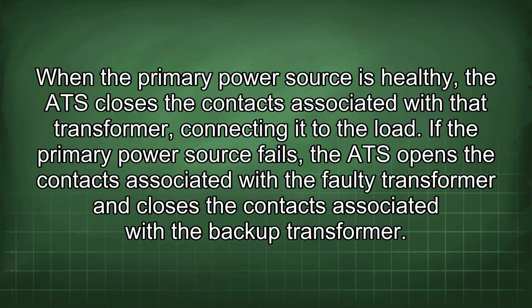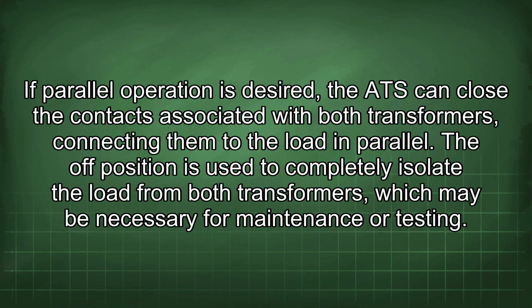When the primary power source is healthy, the ATS closes the contacts associated with that transformer, connecting it to the load. If the primary power source fails, the ATS opens the contacts associated with the faulty transformer and closes the contacts associated with the backup transformer. If parallel operation is desired, the ATS can close the contacts associated with both transformers, connecting them to the load in parallel. The off position is used to completely isolate the load from both transformers, which may be necessary for maintenance or testing.